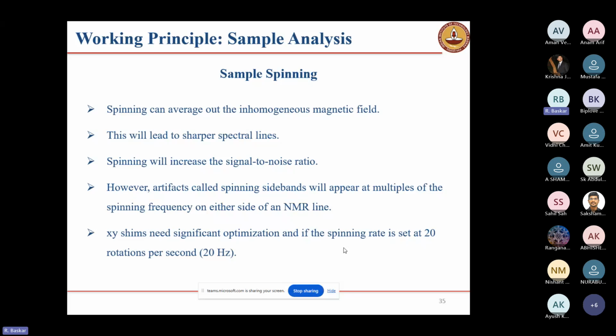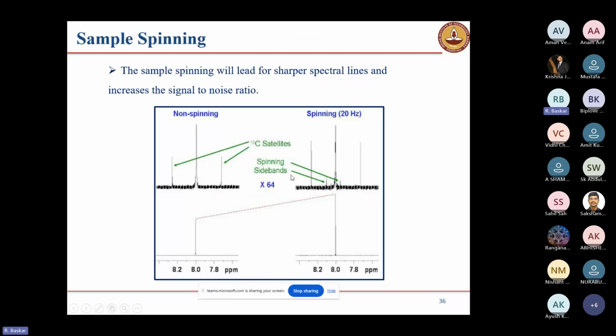When we spin too much, we get spinning sidebands. Why? Because when it spins inside the magnet, the gimbal tolerance is never at its maximum value, and a small NMR tube wobbling will be there. It will generate a secondary magnetic field that will give the spinning sidebands. The optimized spin rate is 20 Hertz. See, this is an example with spinning and without spinning. Here, this is a non-spinning NMR spectrum, and the signal intensity is too low. When we are spinning, the signal intensity will be higher. We can see the small spinning sidebands.